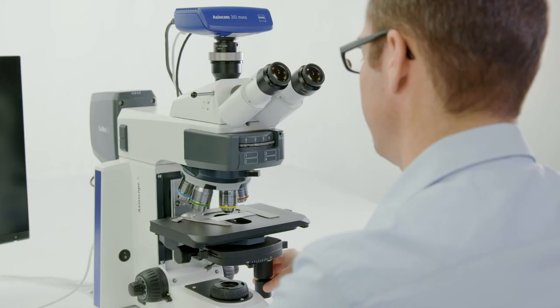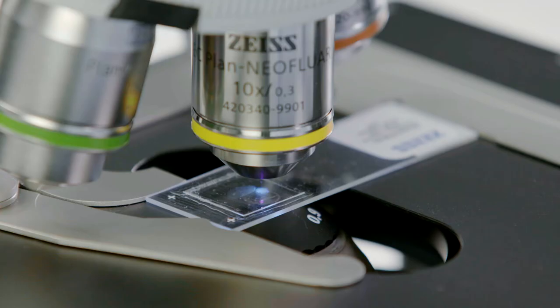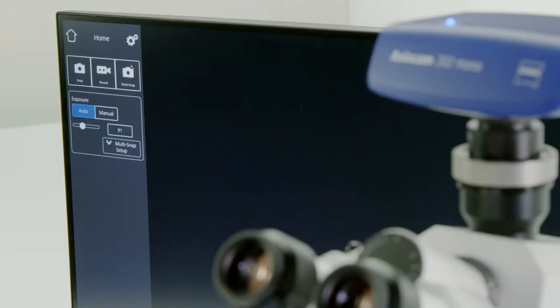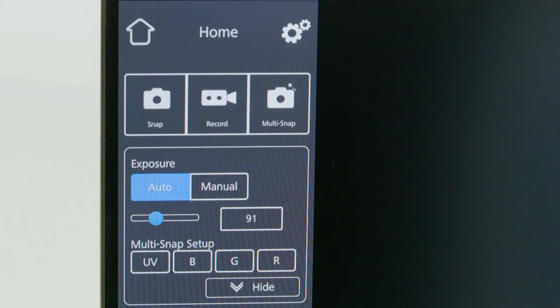Switch to the reflector position containing an appropriate multi-bandpass fluorescence filter, then define the relevant fluorescent LEDs for excitation suitable for your sample via the on-screen display. For the sample shown, it is UV, blue, and green.